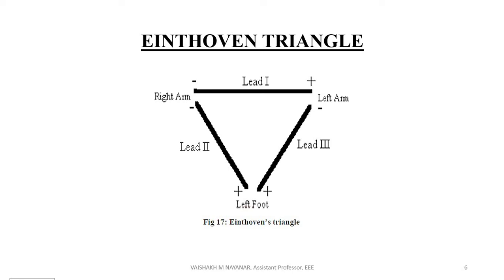So, the relationship between Einthoven's triangle leads: in Lead 1, the right arm is connected to the negative terminal of the differential amplifier (the inverting terminal) and the left arm is the non-inverting terminal. In Lead 2, the right arm is negative and the left foot is positive. In Lead 3, the left foot is positive and the left arm is negative. We conclude the Lead 1, Lead 2, and Lead 3 measurements from this triangle.